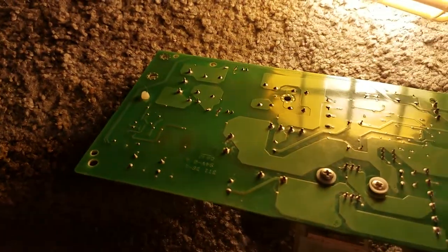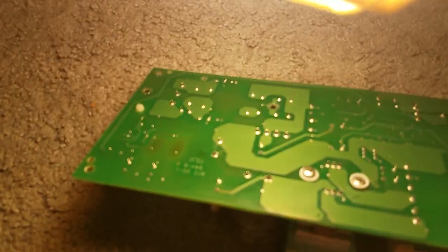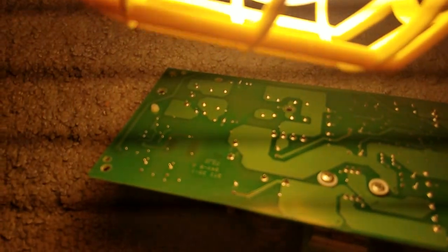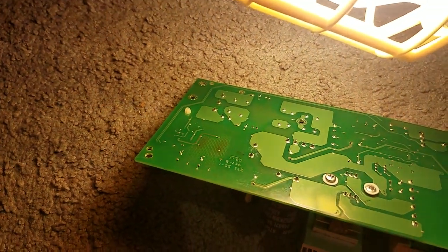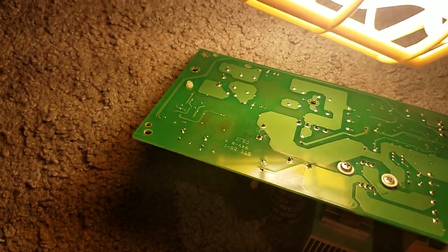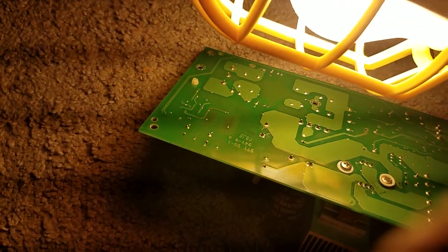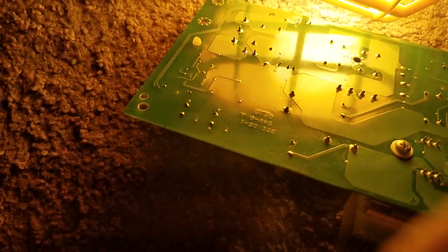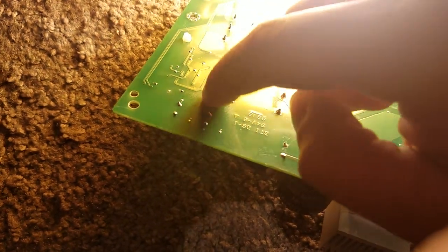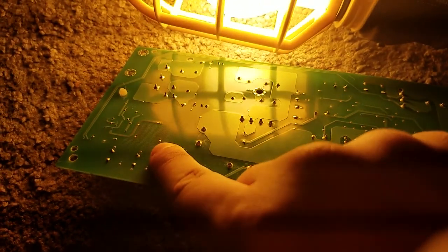I guess this is why they took the panel out of the building, because I guess the technicians didn't bother to replace the board, and they ended up spending a lot of money getting a whole new system. That's a big bummer for them, not throwing them under the bus, but they probably didn't know. I'm inspecting the board closely because I found the major damage right there. This area right here is completely fried. So I guess this is what was causing my AC fault trouble, guys.